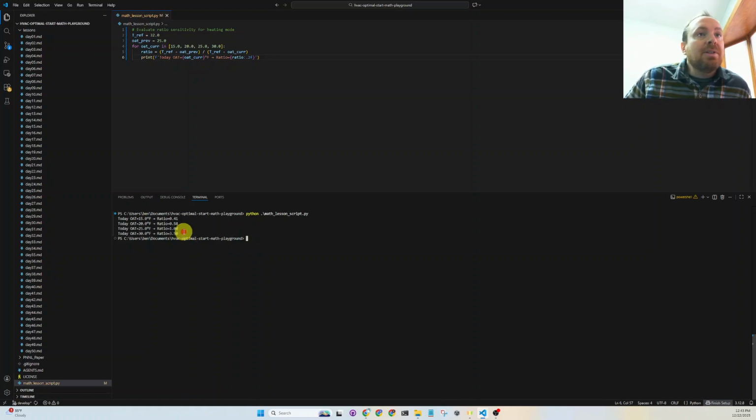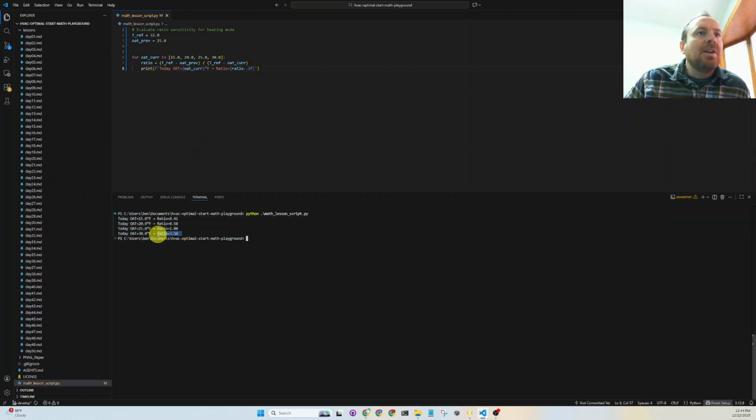Okay, so this is our ratios here, degrees Fahrenheit, and we did talk about formally how the ratio blows up as the outside air temperature reaches the T-ref point. So if you remember in the paper, they described T-ref, a high and a low. So a high was 100 degrees Fahrenheit, and T-ref for heating was 32. There's also metric equivalents to that.